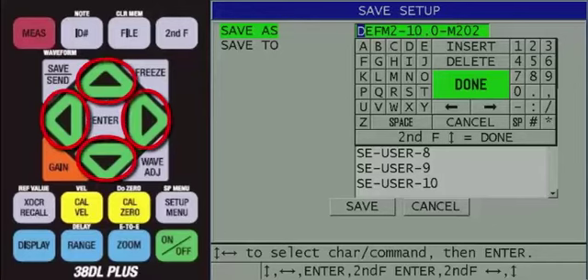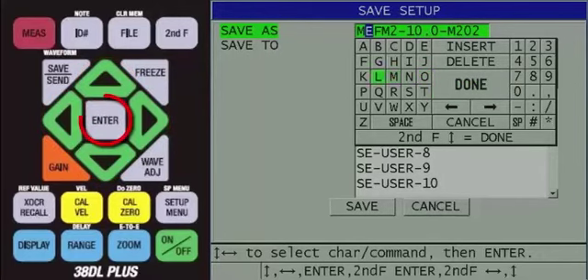Use the arrow keys to highlight a character, then press the Enter key to input the character into the Save As line. As you input characters, the existing setup name will start to be overwritten. We typically recommend entering the material being measured, followed by the transducer that is being used. Since this is a generic how-to video, we will name the custom setup Material-XDCR.